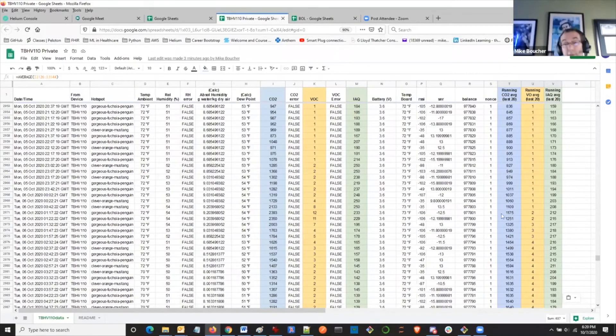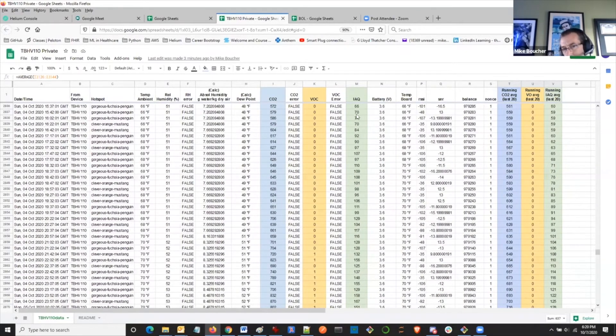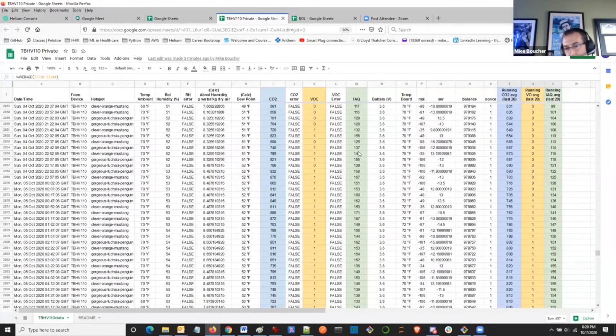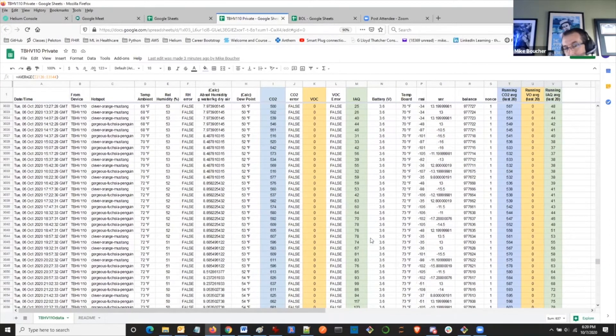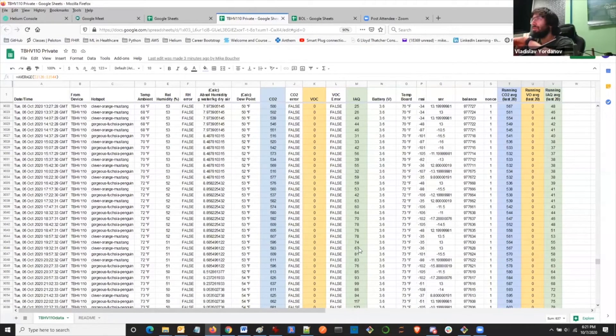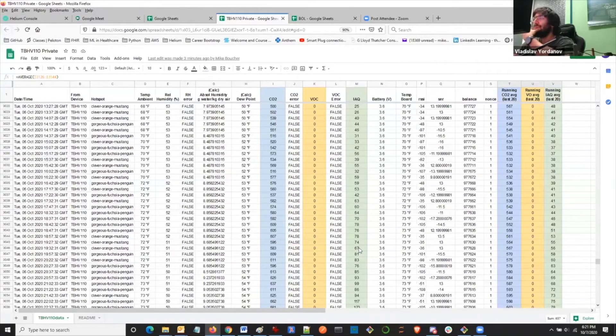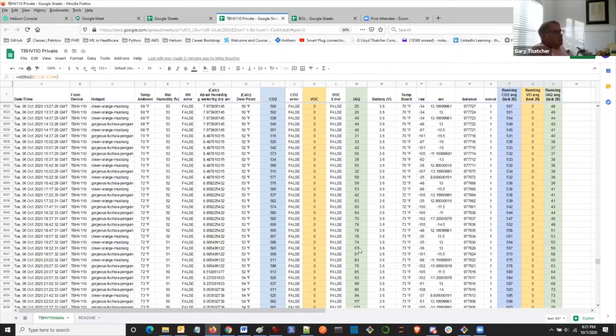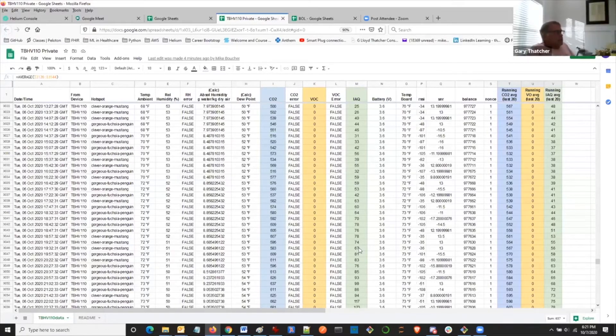This is the actual spreadsheet. If you look over time, the IAQ should be between 50 and 100. Keep in mind there's not always a direct correlation between CO2 and VOCs. There's not a direct correlation in some cases — the size of the particulates that the chip is sensing will sometimes influence the VOC count. But if you average it over time, you will see a correlation in many cases between CO2 and VOCs.